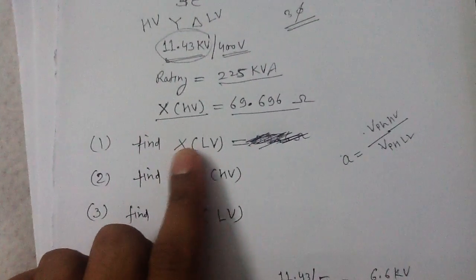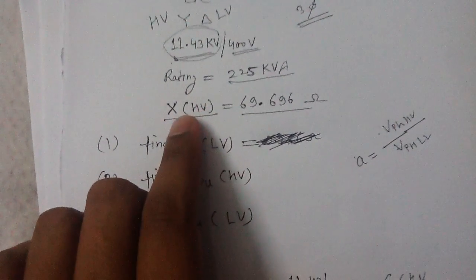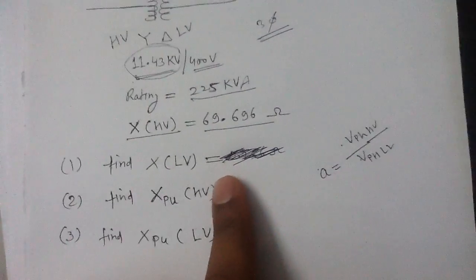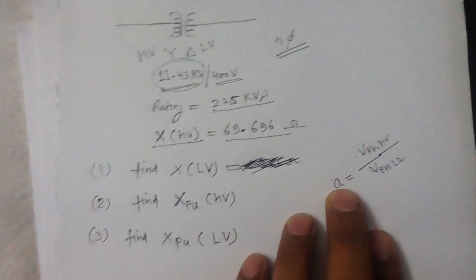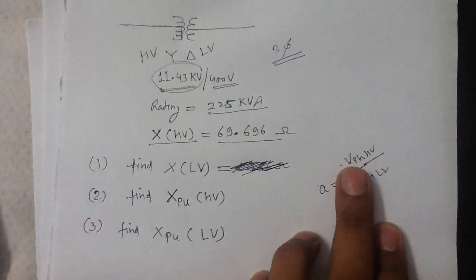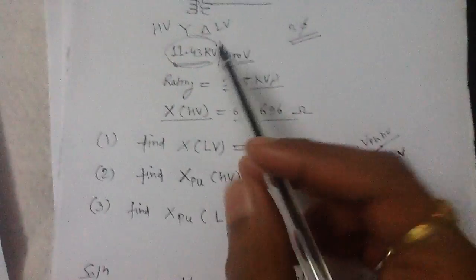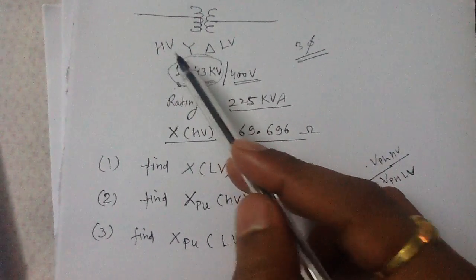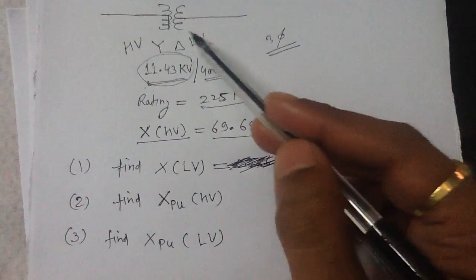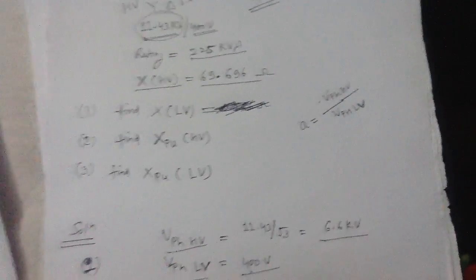To find the reactance referred to the LV side, we need to transform the HV side reactance to the LV side. We need a transformation ratio, which is always greater than one. The transformation ratio is the phase voltage of the HV side divided by the phase voltage of the LV side. The HV side is connected in star, so the phase voltage is 11.43 kV divided by root 3. The LV side is connected in delta, so its phase voltage is 400 volts.